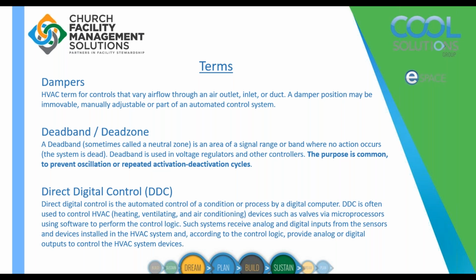So if you're setting your system at 70 heat and 72 cool, you've pretty much negated any deadband in there, and so your system is constantly going to be energizing one way or the other, or thinking it needs to, potentially. If the system is always thinking it needs to run, that means it's always energized, which means you're always spending money. So rather than doing a 70 to 72, if your comfort set point is 70 degrees, consider putting your heating set point at about 66, 67, and your cooling set point at about 71, 72. That'll keep it within that range, just below 72 and just above 68 generally.